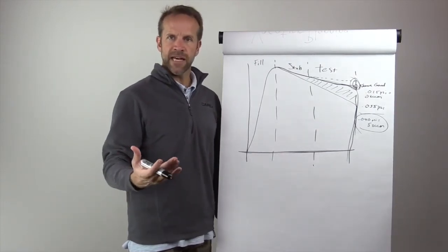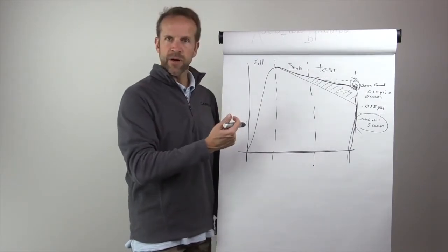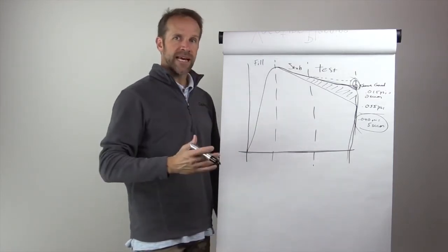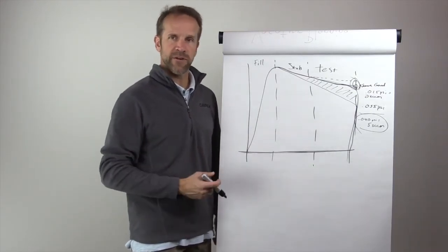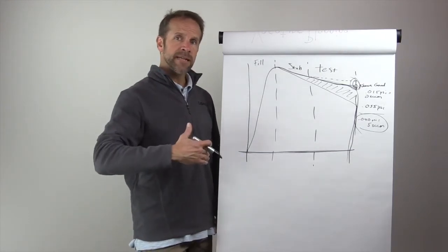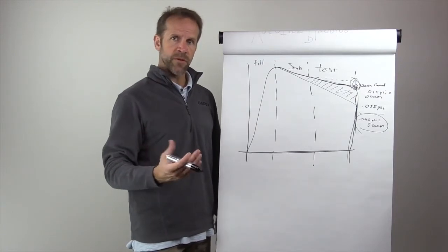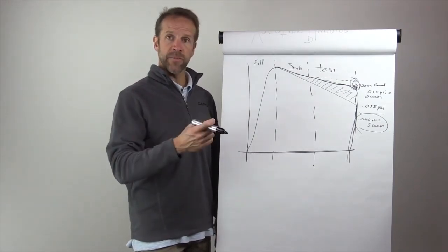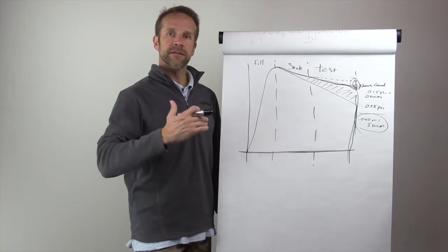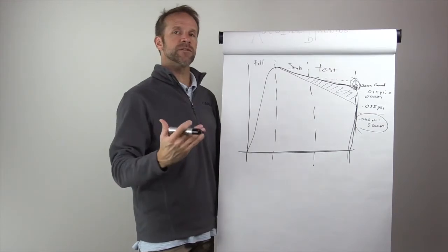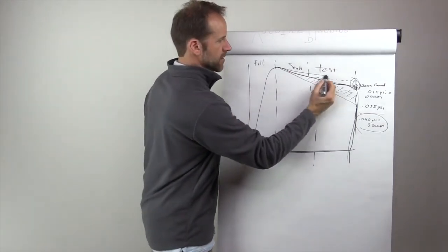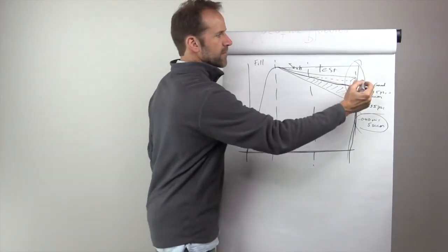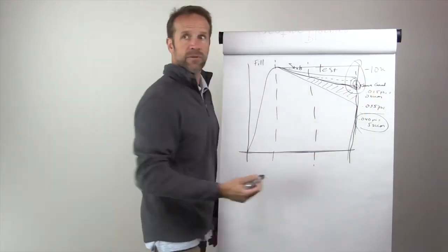It's okay to have negative leak rates when you have a pressure decay calibration setup. It's very common, but that value should be right around, say, no greater than negative 0.5 if you've got a great calibration. If it gets to be more than that, then that can mean that there are other issues going on. For example, if you are using a connector that is activated with air, and that connector is leaking, it could leak into the part. If it leaks into the part, the pressure is going to rise in the part, and that's going to cause a very negative leak. So we are increasing in pressure. This is going to be very negative. We're talking negative 10 SCCM.